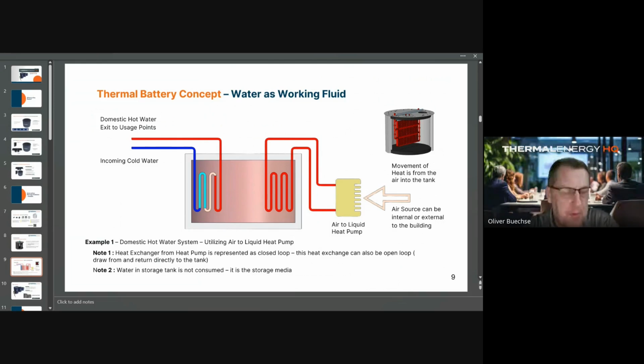And I recall one number that really blew me away when you had calculated that the surface area of this nylon heat exchanger is 95 square feet. That's more than the internal area of the entire tank. So that's really impressive. Yeah, clever people that we purchased that design from. And it started out as a DuPont exercise so they could sell nylon into the automotive industry. And then they rolled that company off to a firm in Canada called Cesaroni that manufactures those for replacement heat exchanger sets in cooling towers and wherever corrosion is prevalent in an HVAC and/or process fluid situation.